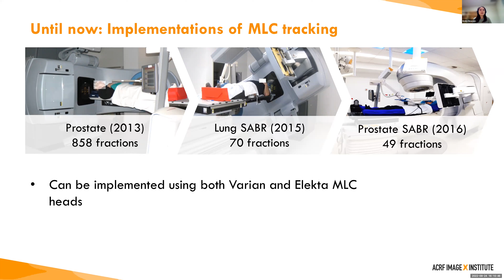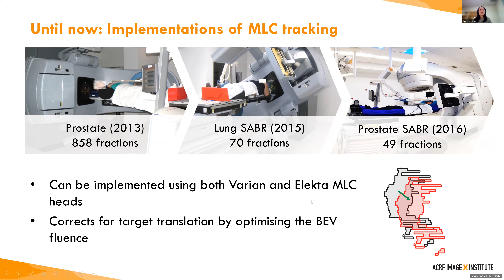So, just a quick recap of how MLC tracking works. If we have a planned aperture, shown here in black, that's tracking a target that undergoes motion indicated by the green arrow, we want to calculate an adapted aperture, shown here in red, which is essentially the shape of the planned aperture, but now translated to the new target position. However, we know that translation isn't telling the whole story of what's going on during treatment. So a lot of our more recent MLC tracking research has been looking to extend this to account for other anatomical changes.